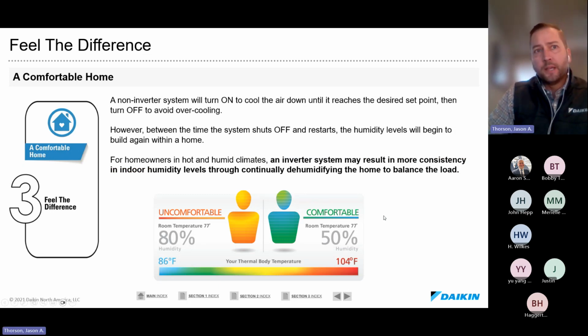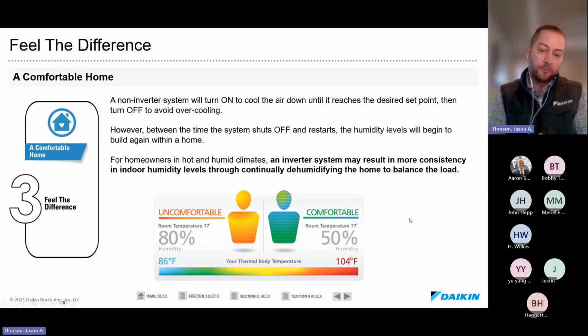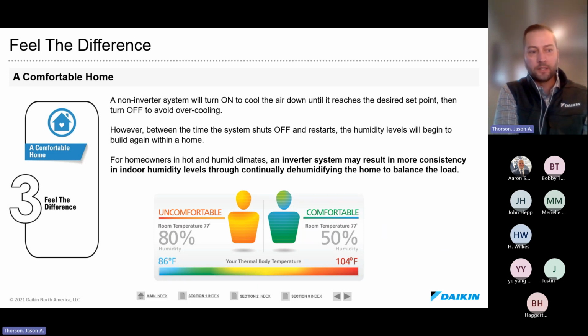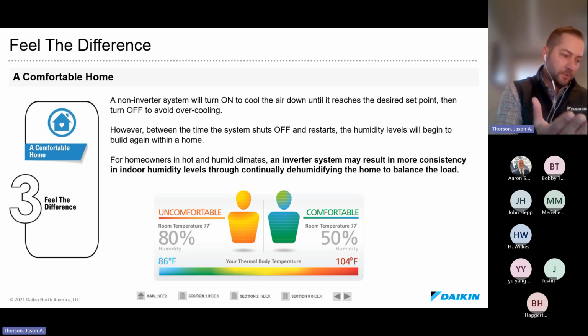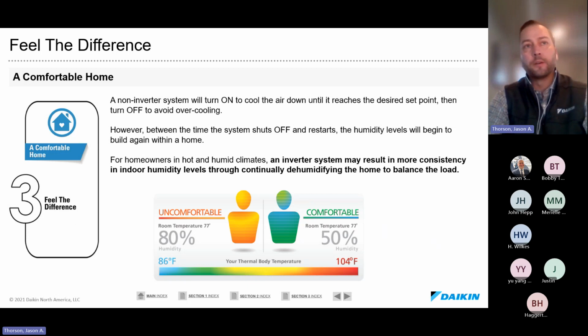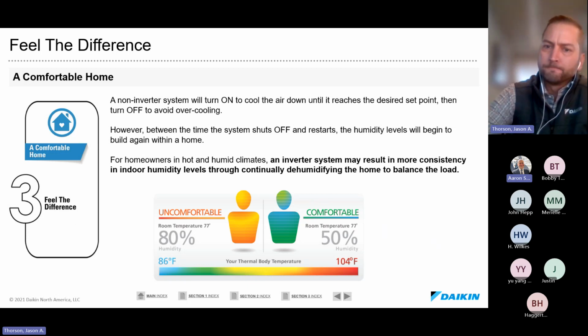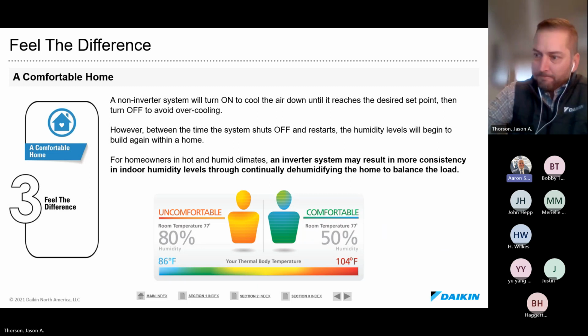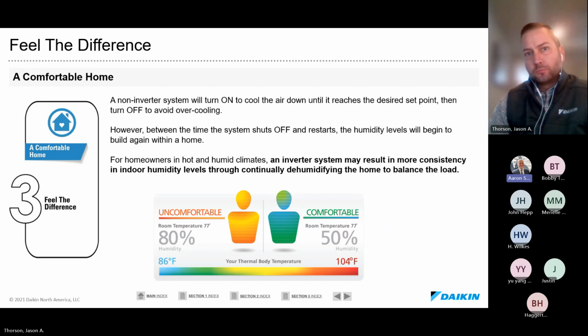On the humidity example, there's no better baseline system to combat humidity than inverter. Even at a mild cooling set point of 72, it takes very little cold air to keep the space comfortable, still pulling air over the coil, removing moisture, displacing humidity, and making the relative temperature that much more comfortable. With a single speed, single stage system, it's on-off, humidity comes back, it kicks on again, very inefficient. The key is you need air running across that coil for a number of minutes before you start to dehumidify.